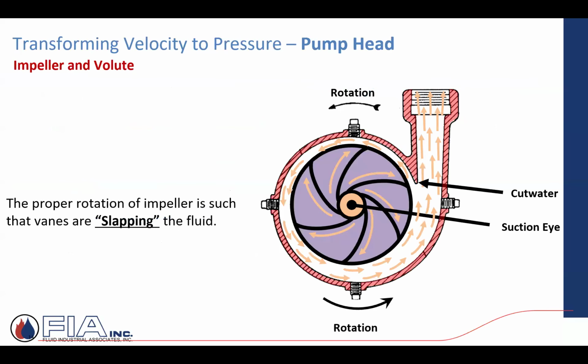And most importantly, what's going to happen here is, as it's rotating around in this rotation, it gets to this kind of moment of, which way do I go? Do I discharge out through the discharge orifice, or do I recirculate internally at what they call the cut water? And from an efficiency standpoint, obviously, we want the majority of that water that the impeller is spinning out to go to the system. I'm using the electricity. I'm spending money on a motor. I want all that water that I've added energy to to go out to the system.